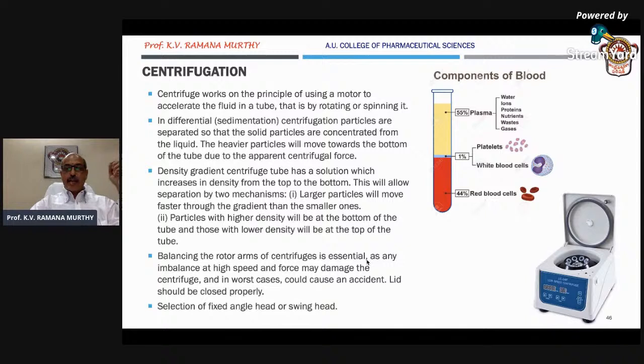Centrifugation: the type of head used is very important. Sometimes we use the fixed angle head, sometimes the swing head, depending on the application. For normal separation, the fixed angle head works, but for highly efficient separation of particles from liquid, it's better to use a swing head, which gives more effect of G. Using the RPM of the centrifuge and acceleration due to gravity, there's a formula by which, subjecting it to 10G, 15G, 20G, we can achieve more separation of solids from the liquids.